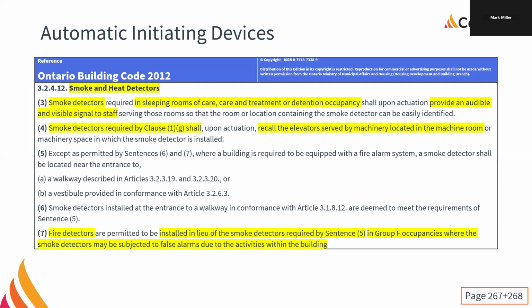So our smoke detectors required in sleeping rooms of care and treatment, or detention occupancies shall, upon actuation, provide an audible and visible signal to staff serving those rooms so that the room or location containing the smoke detector can be easily identified. And we tie that into the nurse call system. Right? With the modern nurse call systems that are basically Cat 5 cable and all that, typically there's a set of contacts on the dome light for the room.